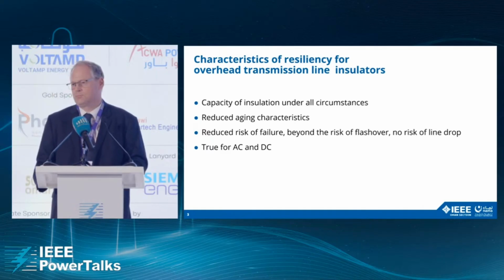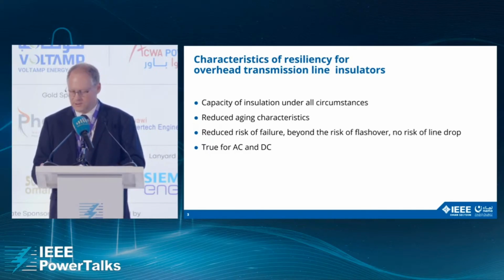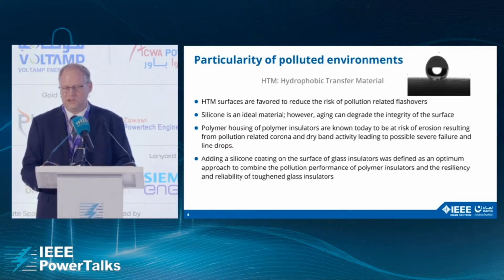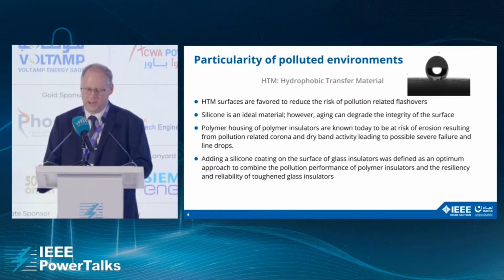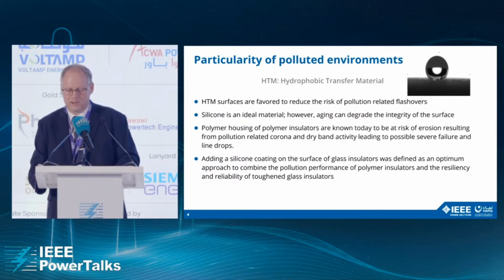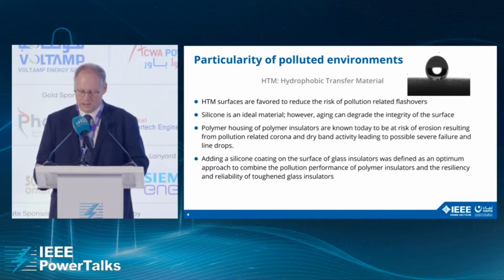For DC lines, pollution is much more harmful and severe than on AC lines, and pollution becomes the most predominant phenomenon to consider. So to mitigate the effect of pollution, a good solution is to use HTM materials, HTM meaning hydrophobic transfer material. It is now well known that HTM surfaces are favored to reduce the risk of flashover induced by pollution. However, silicone is an ideal material, but aging can degrade the integrity of the insulator surface. Polymer housings of polymer insulators are known today to be at risk of erosion resulting from pollution-related corona and dry band activity, leading to possible severe failure and line drops.